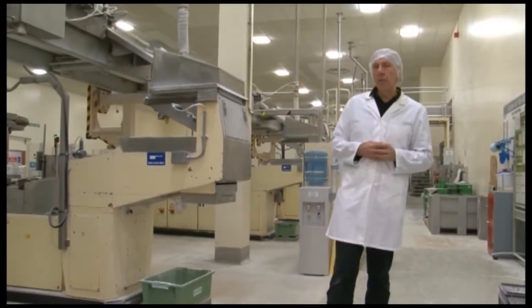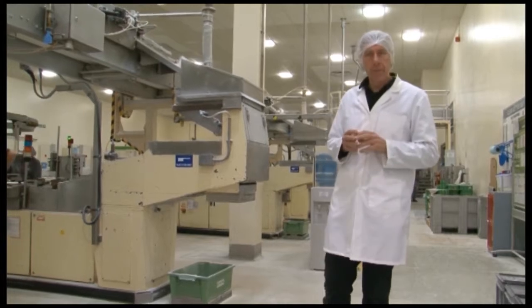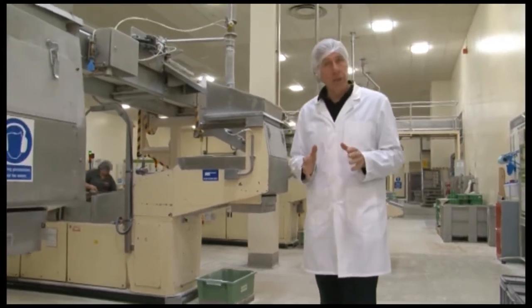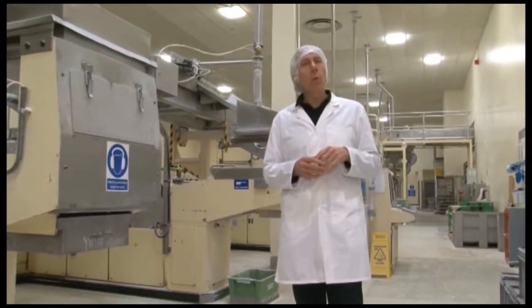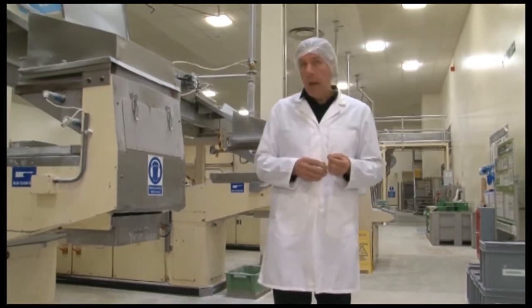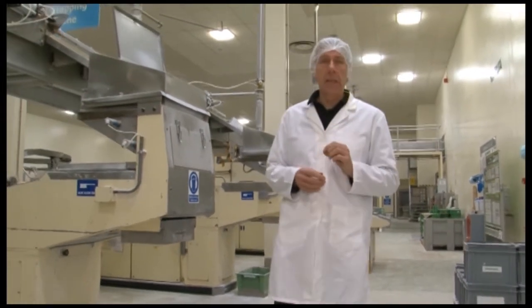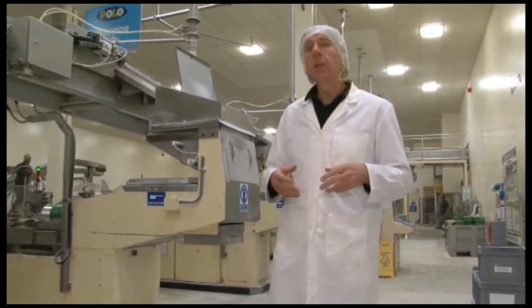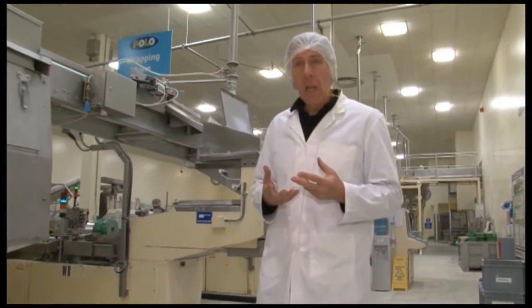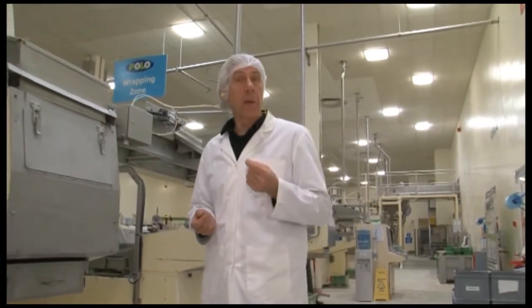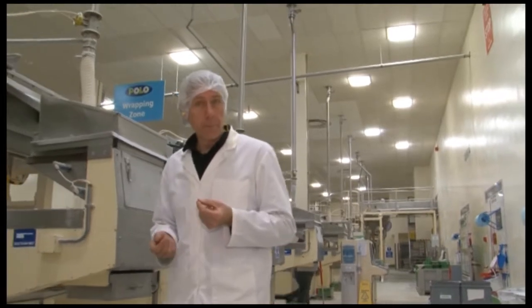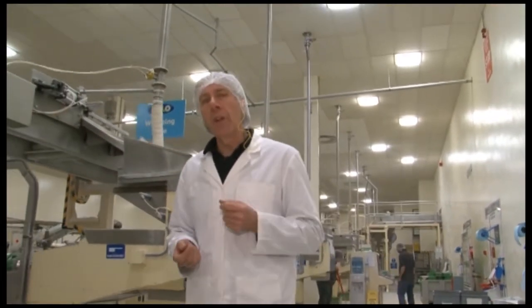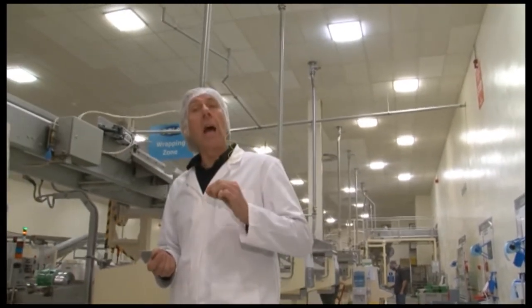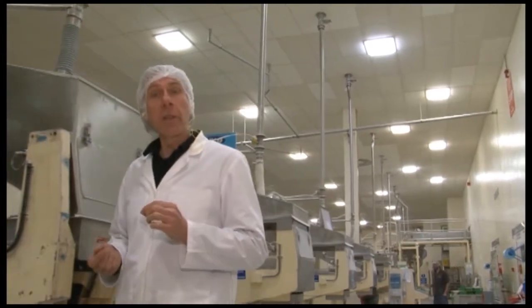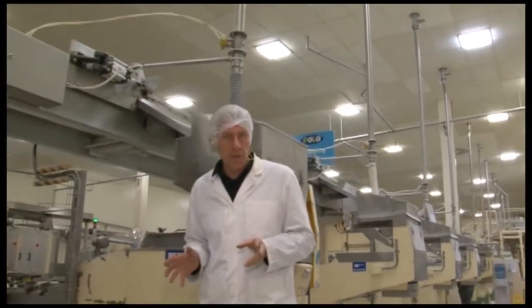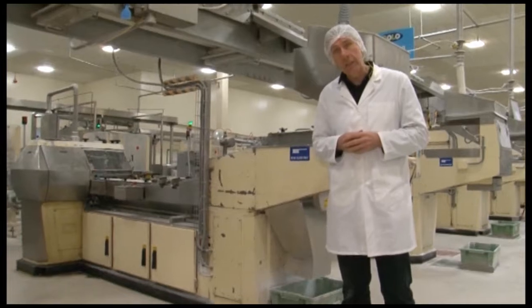That brings us to the end of the regulations concerned with equipment itself. The next 3 regulations, 13, 14 and 15, relate to the way work is performed on equipment. However, they should not be seen as a separate entity, since if equipment is well designed, well built and well installed, complying with regulations 13 and 14 in particular will be that much easier. Also, regulations 12 and 13 are both an integral part of the isolation procedure, which we're going to run through now, at low voltage, so you can appreciate the practicalities involved.